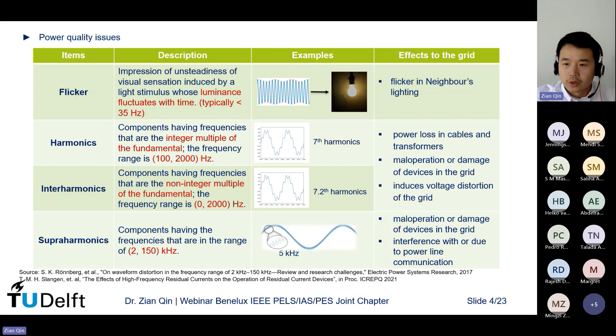As I mentioned, the higher the frequency, the larger the magnitude of current needed to trip the RCD device, and the same also holds for these supraharmonics. Besides that, because it's already in the frequency range of power line communication, it can also interfere with the power line communication.